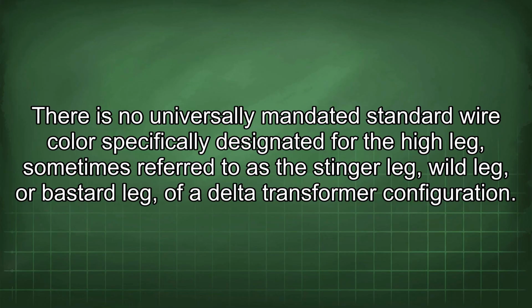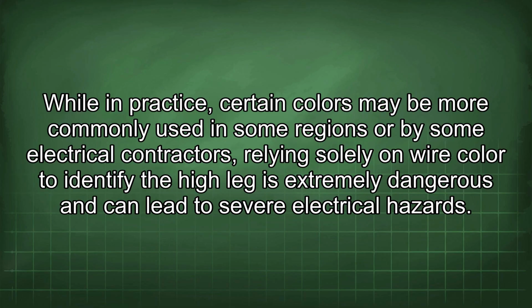There is no universally mandated standard wire color specifically designated for the high leg, sometimes referred to as the stinger leg, wild leg, or bastard leg, of a delta transformer configuration. While in practice, certain colors may be more commonly used in some regions or by some electrical contractors, relying solely on wire color to identify the high leg is extremely dangerous and can lead to severe electrical hazards.